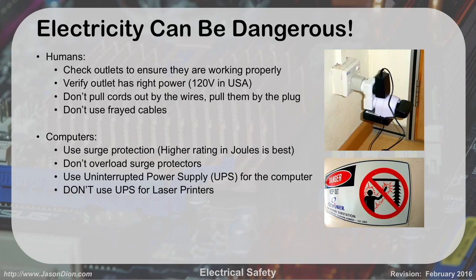And this is something a lot of people don't realize: you don't want to use a UPS for laser printers. If you have a printer like the one in the back of the room here, plugging those into a UPS will drain the UPS too quickly, and can actually cause problems for the UPS and destroy it. Laser printers are not designed for UPS—they take way too much wattage.